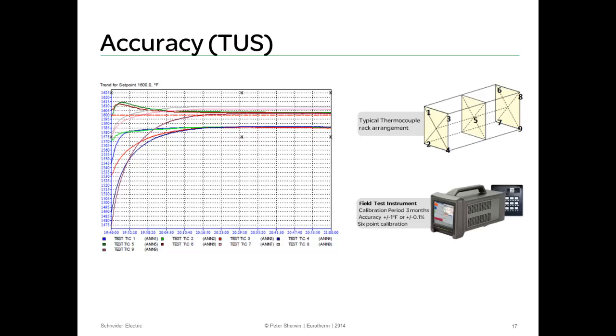Moving to the field instruments for a TUS, these instruments are held to a higher accuracy standard of 0.1% or better, compared to process recorders of 0.2%. Some of these units now have special CJC block built into the recorder to enable higher accuracy and provide what is termed as instant-on capability. No more waiting for a recorder for 30 to 60 minutes to stabilize in ambient conditions to give you accurate results.